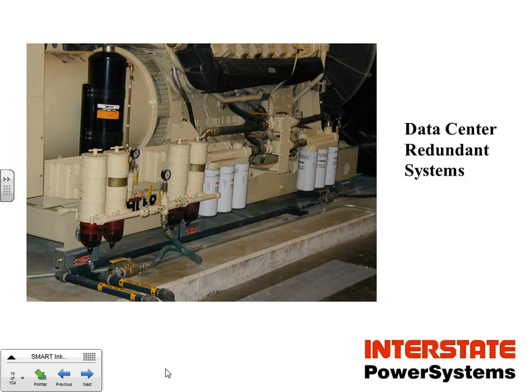Now, data centers also have a lot of redundancy built in. You'll see a couple of sets of fuel filters here, 2 sets of oil filters, a lot of little extra plumbing to make these things work and stay running. And by doing it this way, worst case scenario, if the utility power was gone, they could run these things and even change the oil and the fuel filters while the thing was running. That's the idea of the redundancy.